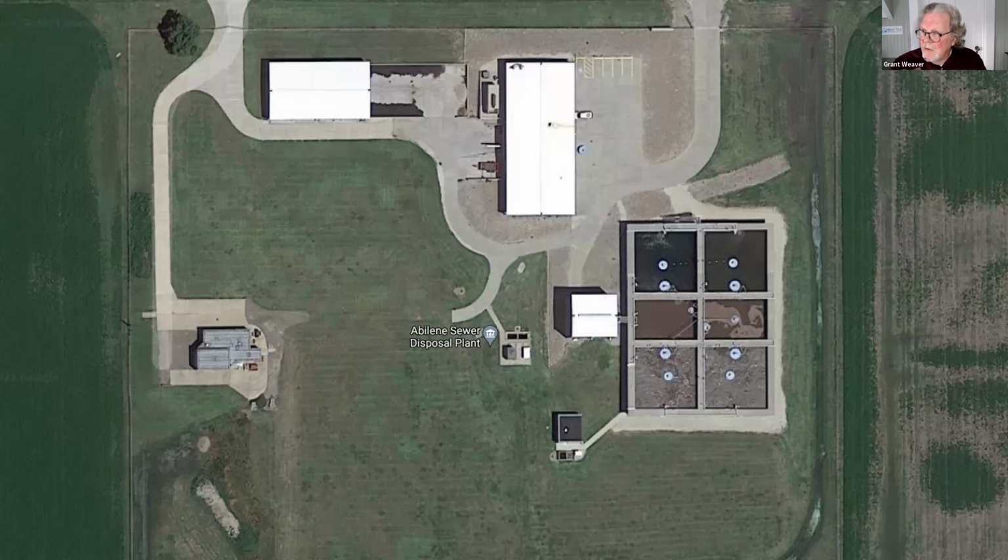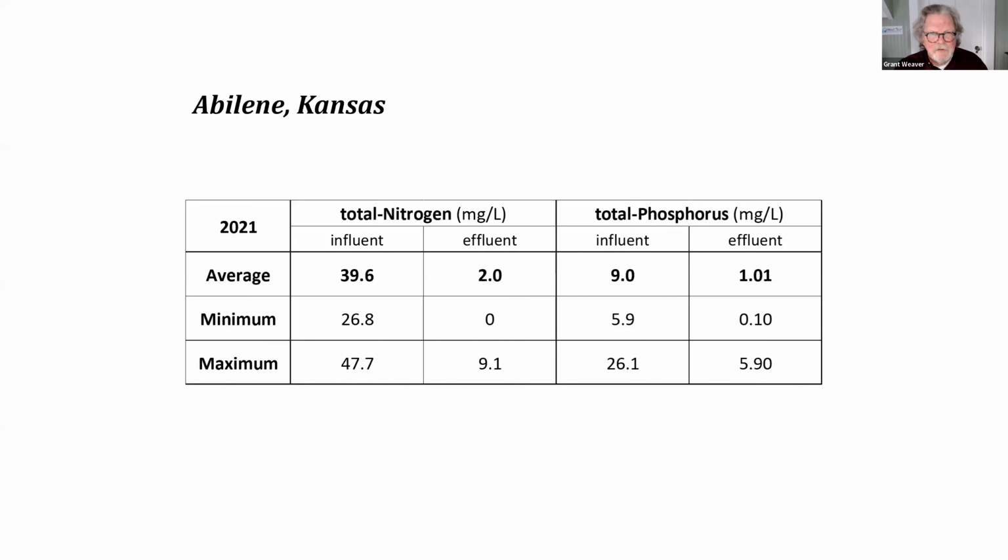So they shortened their settle time so that it was long enough to have nice clear water on top and sludge on the bottom, but not so long that it sat there for hours and the sludge at the bottom started to re-release the phosphorus. They also adjusted the air-on cycle to give it a little more of a boost, make it a little more aerobic, again with the idea they didn't want that re-release. And here are some of the numbers they were able to produce with that treatment plant.